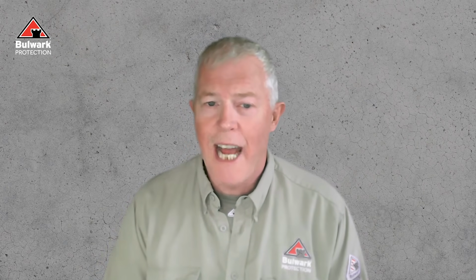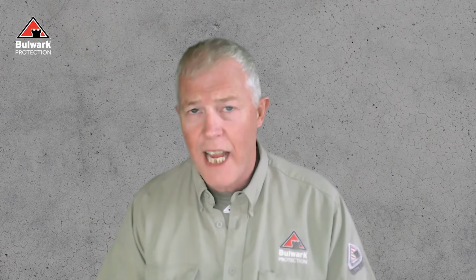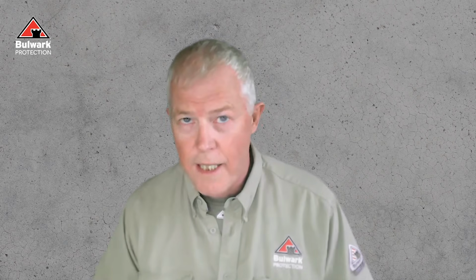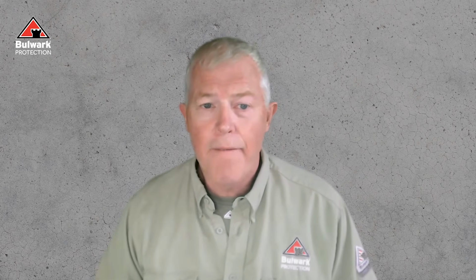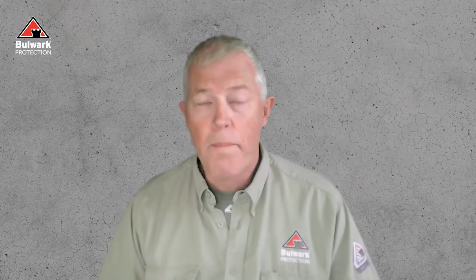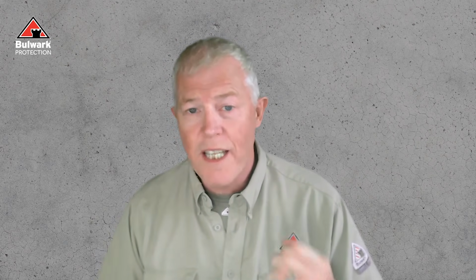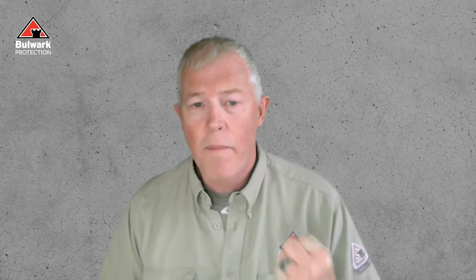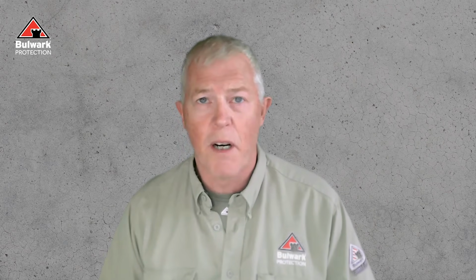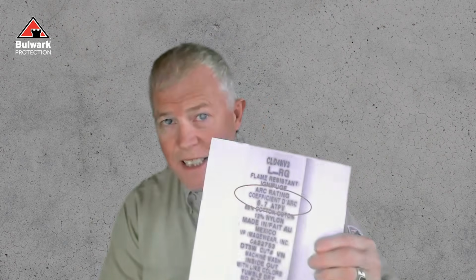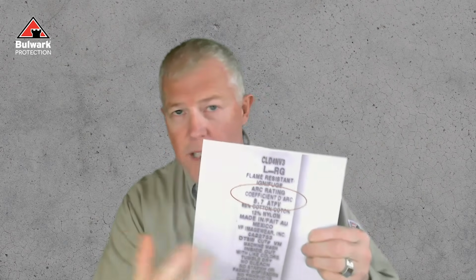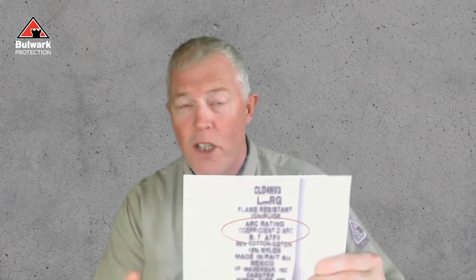The result is expressed in calories per centimeter squared, either as an ARC thermal performance value, or ATPV, and/or an energy break open threshold, an EBT. Both are ARC ratings, and both tell you the same thing: how much energy can I sustain before the onset of a second-degree burn? Where you see that is in the label. If you see an ATPV or an E sub BT, 8.7 calories per centimeter squared, for example, that's your ARC rating. You already know in order to get this, first and foremost, I have to be FR.